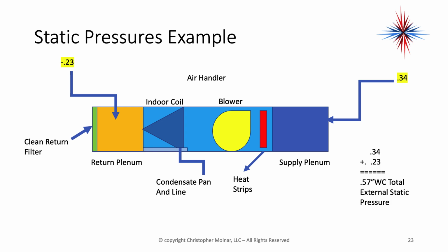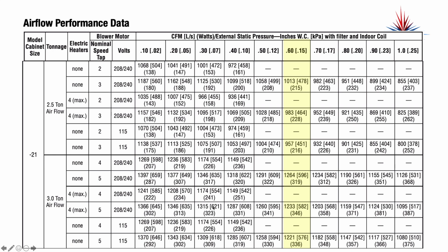So if I use the specifications for the same unit I just did, I find the airflow performance data. 0.57 is someplace between 0.5 and 0.60, but I don't ever round down, so I'm going to go to 0.6. If I am on 0.6, and I have a 2.5 ton unit, I'm going to have between 957 and 1013 of airflow. Now again, this means that my motor is at basically its highest speed, because from nominal, remember, I want 1,000. Anything else here is going to be too low. Granted, it's close, but it's still too low.